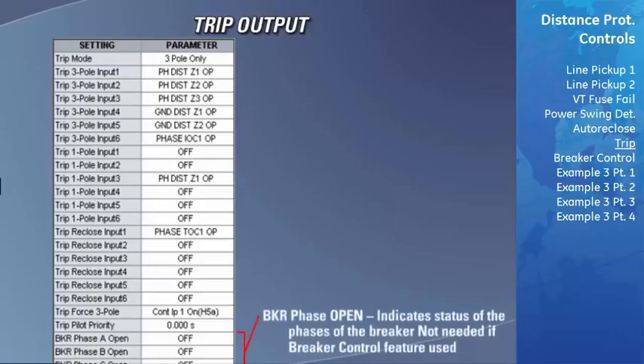The breaker phase A, B, and C open fields are used to indicate the status of the 3 phases of the breaker. If all 3 phases of the breaker are indicated by the same 52A input, you should assign that same input to each of these three fields. If the breaker control function is being used, these settings can be left at the defaults. We will be covering the breaker control function in the next section.